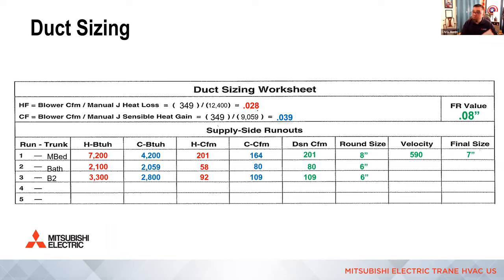And we still want to verify a 7-inch is not going to be too fast now. So we would go to 7-inch on our duct calculator, look in the window at 200 CFM and see that it's just about 750 feet per minute, which is right in the middle and perfect for design. So we would continue on with a 7-inch for that master bedroom in that example, right? Keep in mind though, we would probably split that into two in reality. This is just a classroom example. Then we would do the same for the others, right?